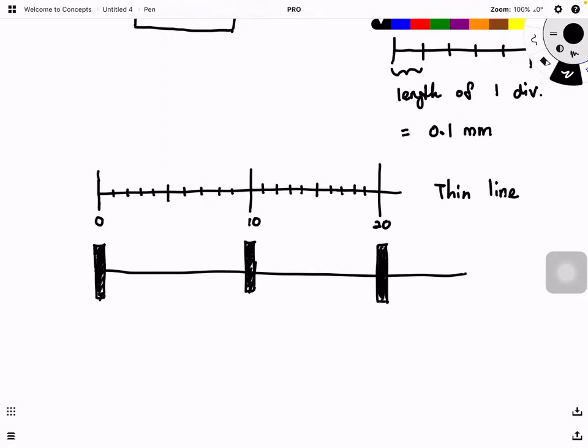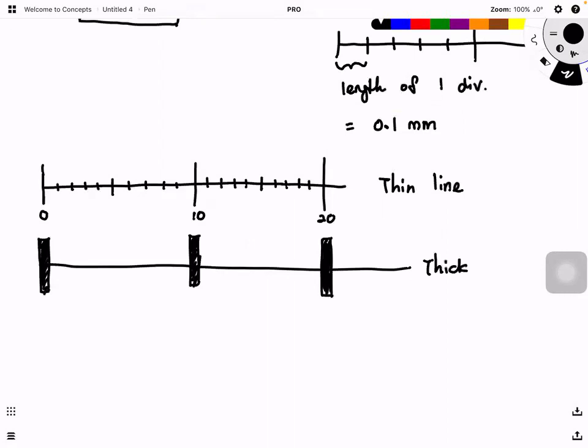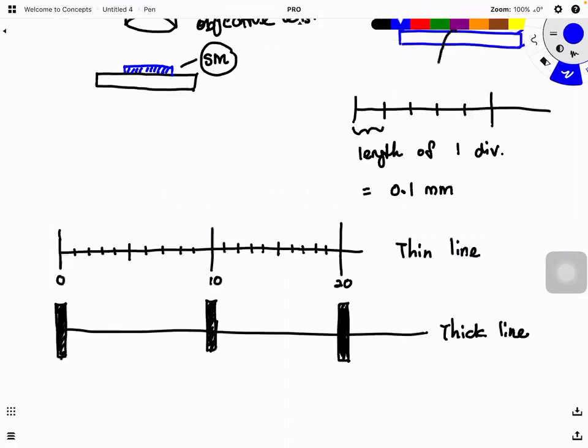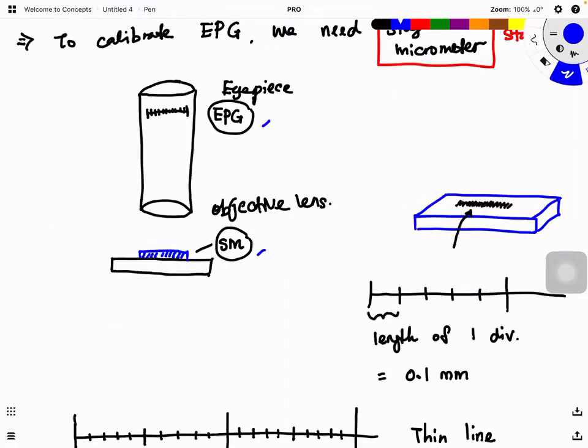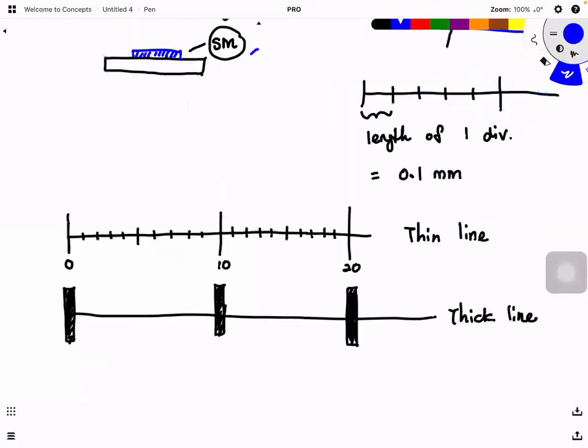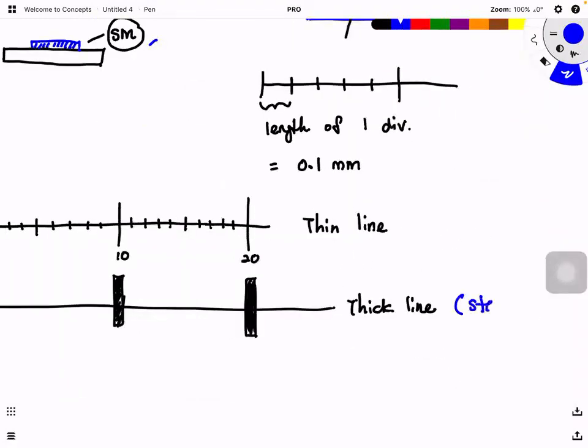So thin line and thick line, now you can see that both of them overlap. Okay? They are overlapping with each other. Thin line actually, because you can imagine, guys, we have the eyepiece graticule and the stage micrometer. The thin line will be the eyepiece graticule. Why the eyepiece graticule? Because we enlarge only one time, by the eyepiece. But for the stage micrometer, the scale is enlarged by the objective lens and enlarged by the eyepiece. So it means 2 times enlargement. So you can see that the thick line is actually the stage micrometer. The thin line is from the eyepiece graticule.